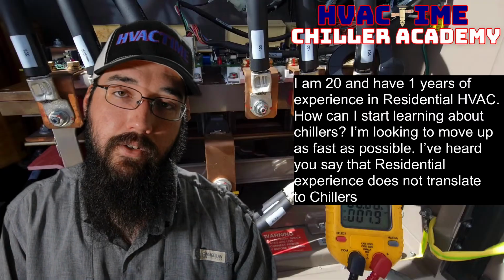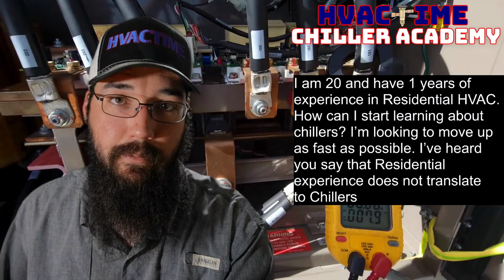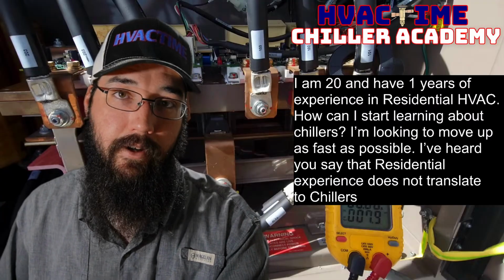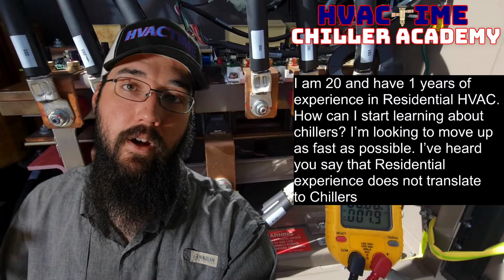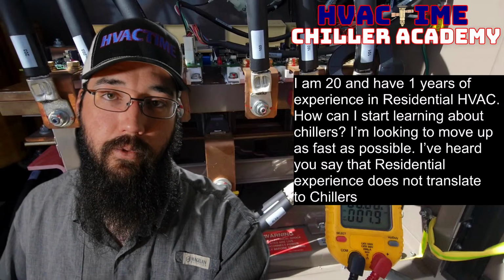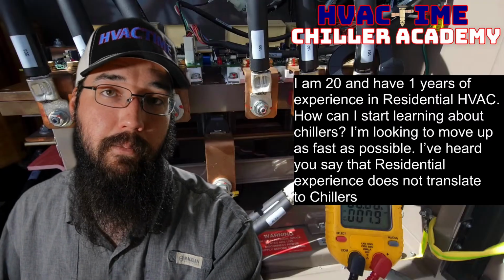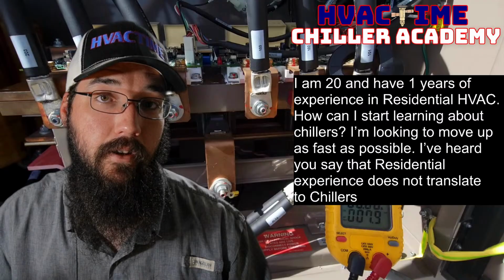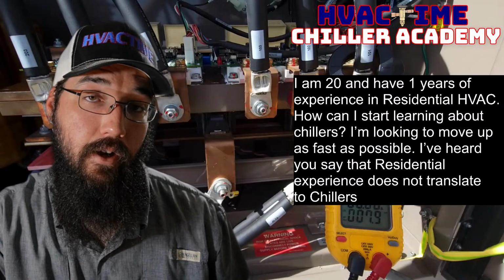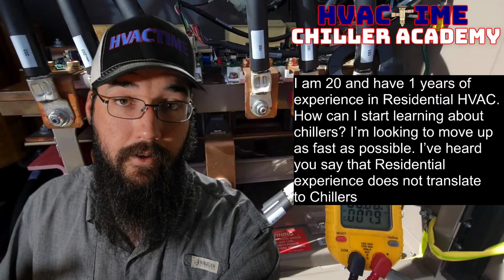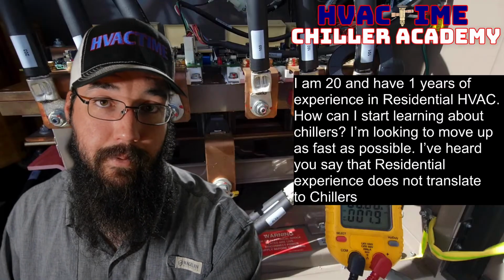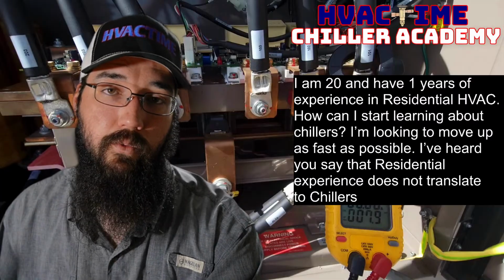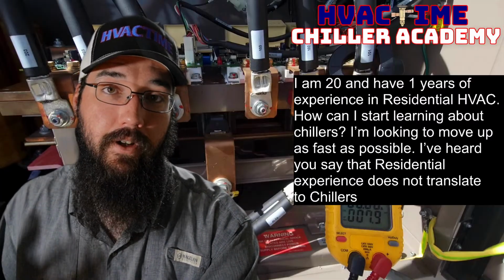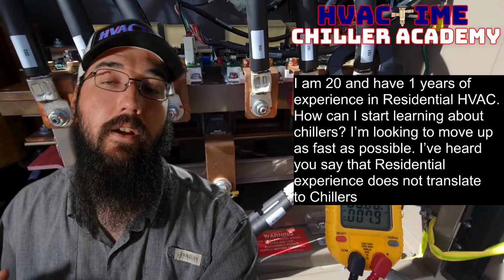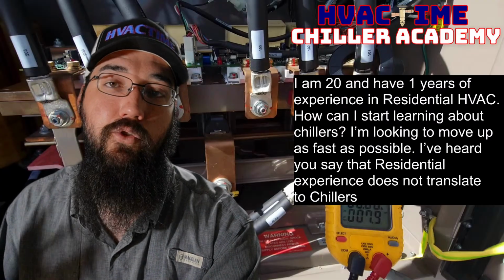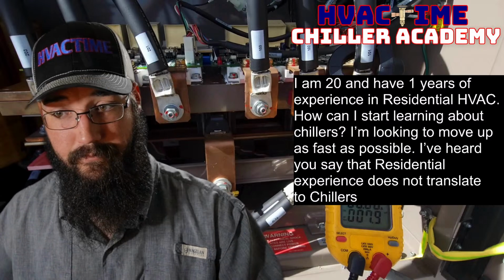Instead of air for CFM, replace that with water and GPM on our chiller's evaporator. So now if we run less water through our evaporator in the form of gallons per minute, let's say a strainer began to plug up. Okay, so instead of an air filter, we now have a water filter, a strainer, that begins to plug up and lowers our GPM. Well, we're going to see the exact same conditions. We're going to see saturation begin to drop. We're going to see the superheat also be affected.